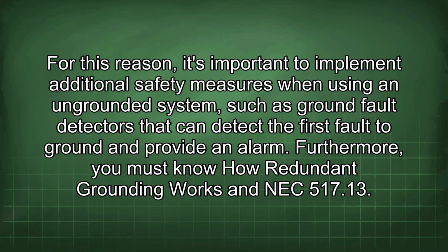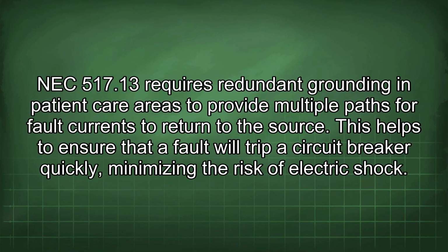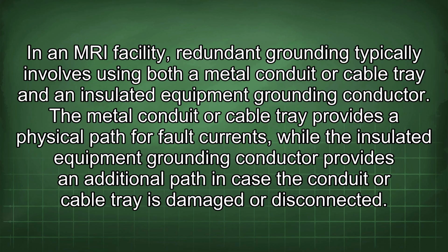Furthermore, you must know how redundant grounding works in NEC 517.13. NEC 517.13 requires redundant grounding in patient care areas to provide multiple paths for fault currents to return to the source. This helps to ensure that a fault will trip a circuit breaker quickly, minimizing the risk of electric shock. In an MRI facility, redundant grounding typically involves using both a metal conduit or cable tray and an insulated equipment grounding conductor. The metal conduit or cable tray provides a physical path for fault currents, while the insulated equipment grounding conductor provides an additional path in case the conduit or cable tray is damaged or disconnected.